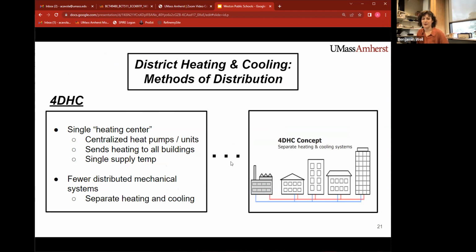There are a couple different configurations for district heating and cooling distribution. One is this 4D heating and cooling system, characterized by a centralized energy center with one centralized heat pump that produces hot and chilled water and sends it to individual buildings. There's a single supply water temperature for all buildings, and heating and cooling water are kept separate.